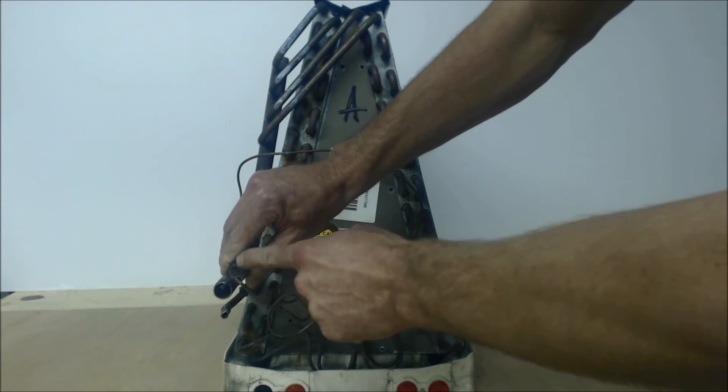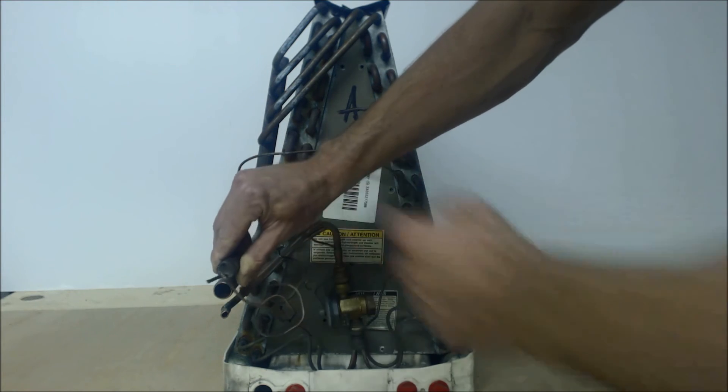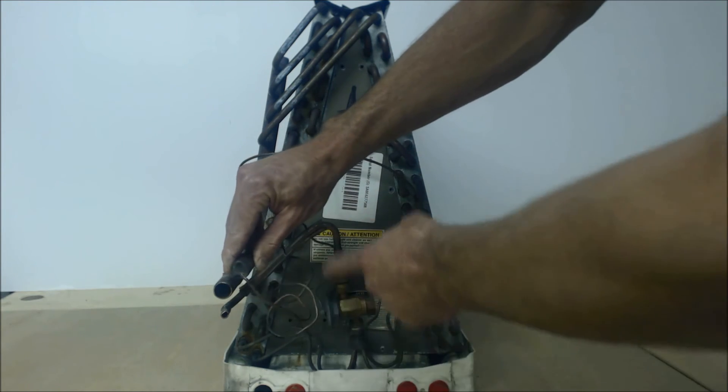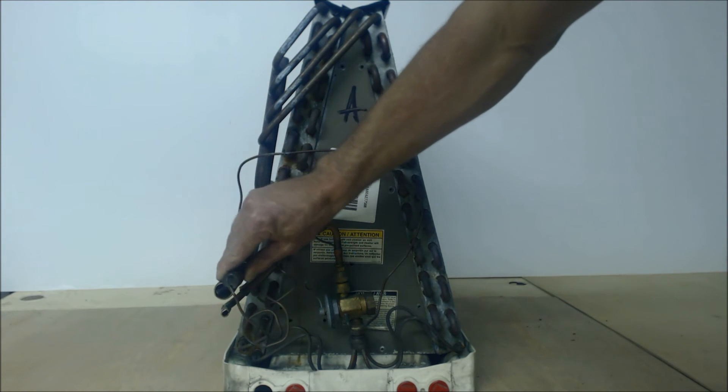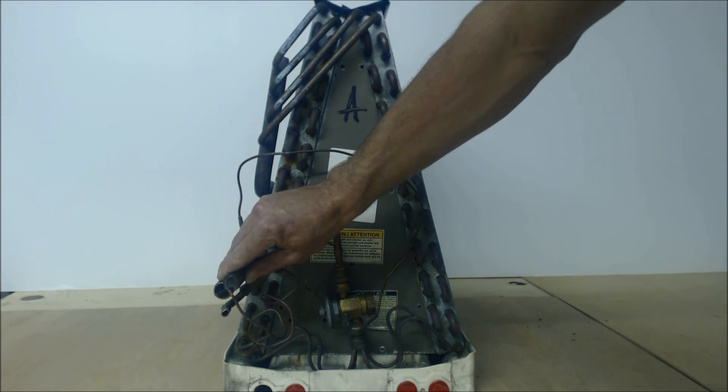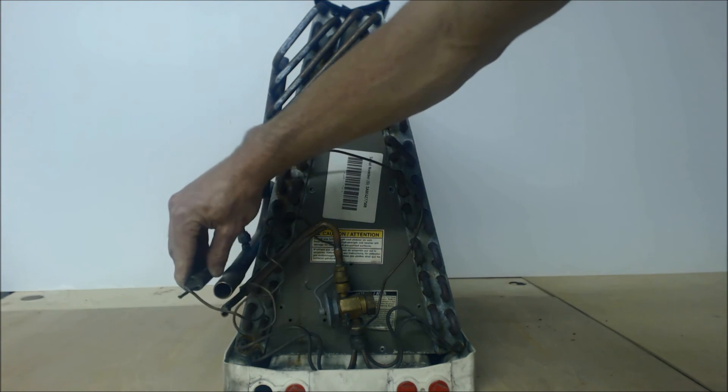That's where the vapor is going to be applied. Then you can mount it to the suction line. Make sure that you're mounting it somewhere where it's not on the bottom. Usually 10 or 2 o'clock is usually the best spots to mount it up.